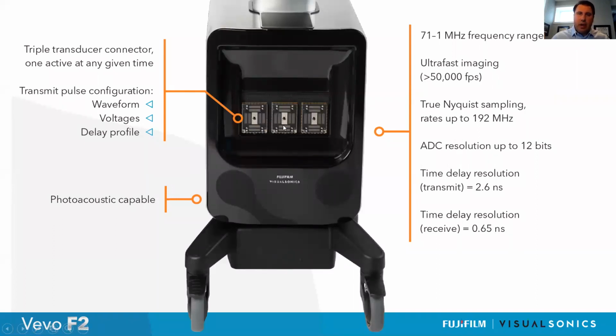Here's the triple transducer connector I mentioned. Three transducers can be connected. One transducer will be active at any given time and can be selected via the touchscreen interface. The pulse configurations, and we'll get more into this, but everything from waveform voltage and delay profile can be controlled at a very low level for any given transducer.